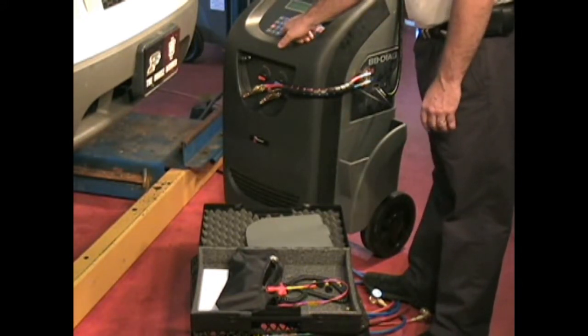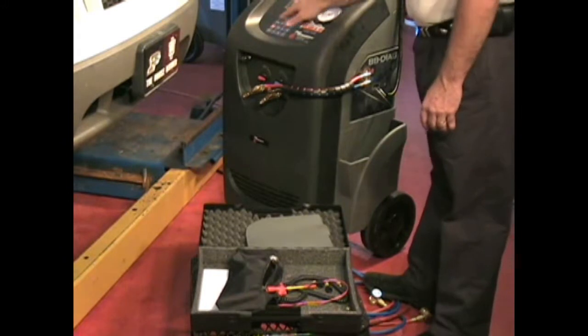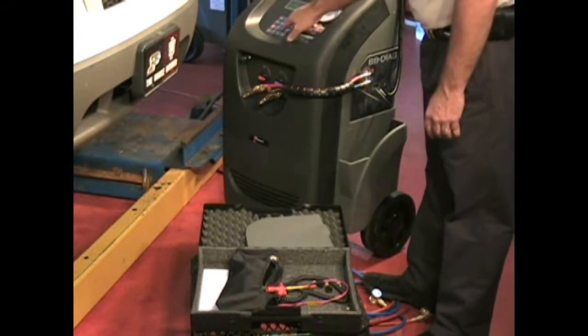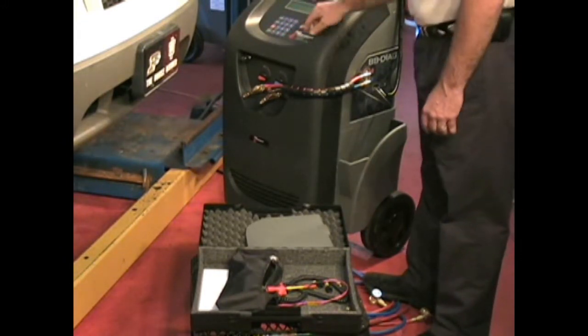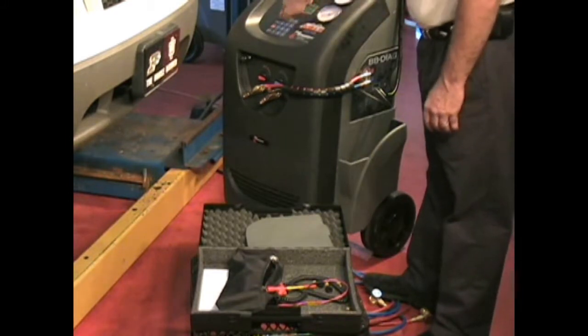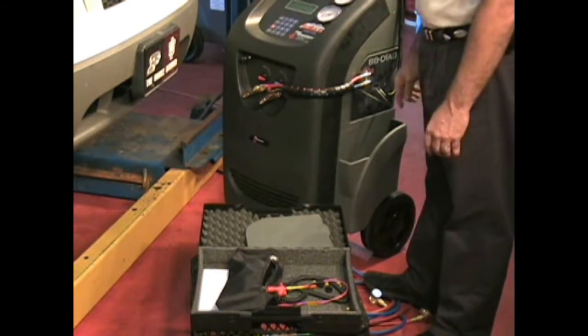Let's say the vent temperature and sensor need calibration. Select Vent Temperature and press Enter. Enter the value from your thermometer and press Start. It's that simple. Your DM300 is now ready to use.